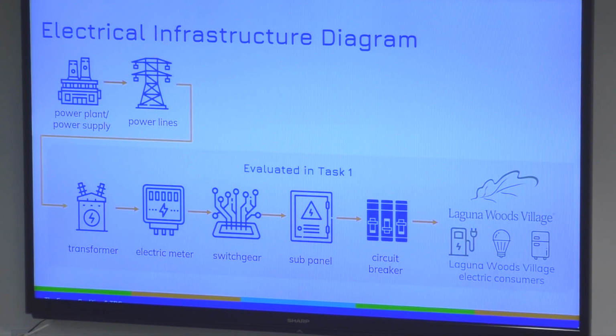Starting with the transformer, a static oil-filled device which transforms the voltage level, either increasing or decreasing it, to keep power and frequency constant. When TEC and TRC came on board as the energy consultant, we heard on numerous occasions about aging infrastructure and SCE transformer failures. Transformers can fail for a number of reasons, including the end of the transformer's useful life, electrical overloads, and manufacturing flaws.